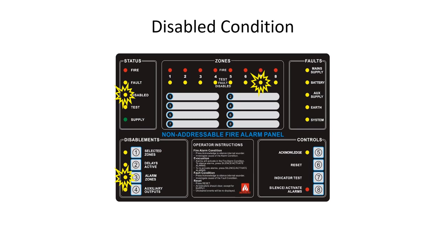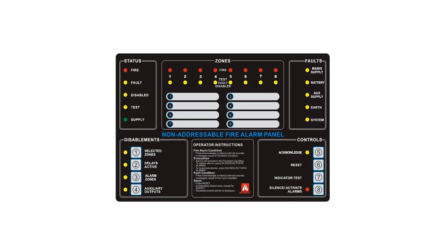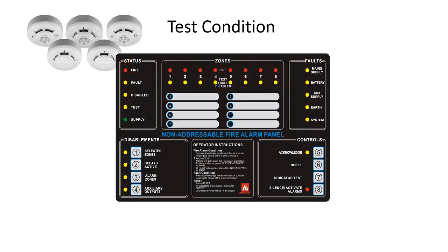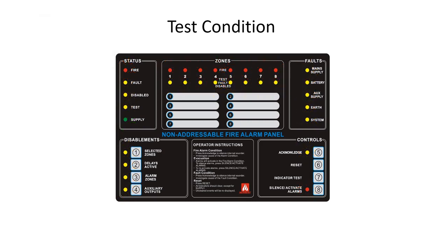In the example shown here, the alarm zone's disabled indicator and the detection zone 7 indicator are on, meaning that a fire signal from zone 7 will not be processed by the control panel. In the test condition, both the control panel indicators and connected devices can be tested. When the panel is in the test condition, the test LED will be on.